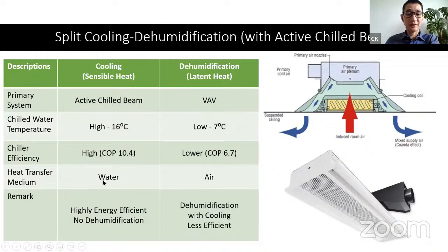Water has a higher specific heat than air, so less energy is used to move water than to move air. So it's very energy efficient, but it does not do any dehumidification because the temperature is high. We need a separate system that does all the dehumidification, the extraction of moisture out of the building. The system that we use is the conventional VAV system, but because the chilled beam already takes care of the sensible heat, the VAV is now sized just to deal with the latent heat. So the airflow rate is very low.